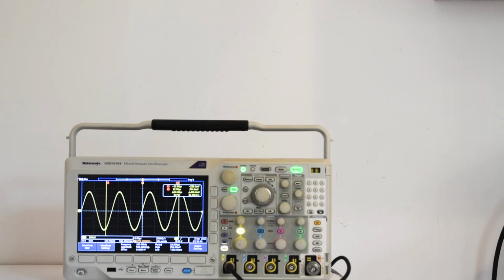Use the horizontal position knob to insert added delay between when the trigger occurs and when you actually capture the data. Insert a negative time to capture more pre-trigger information. With delay mode off, the bottom line shows the time location of the trigger within the acquisition as a percentage.